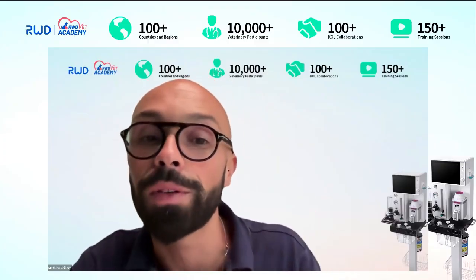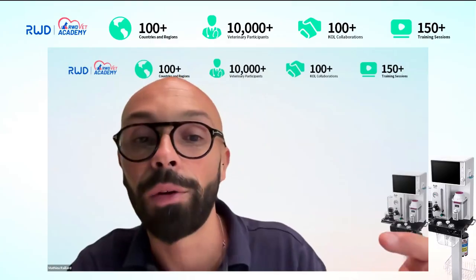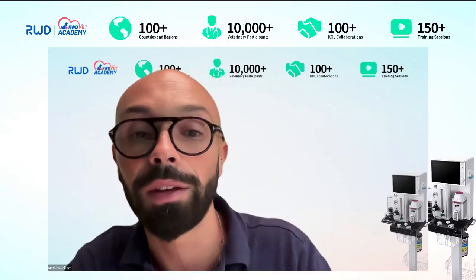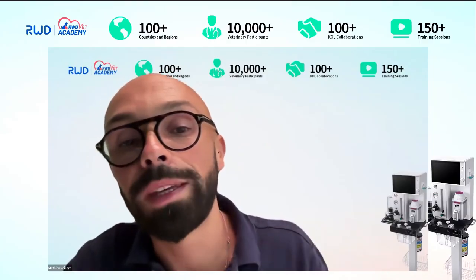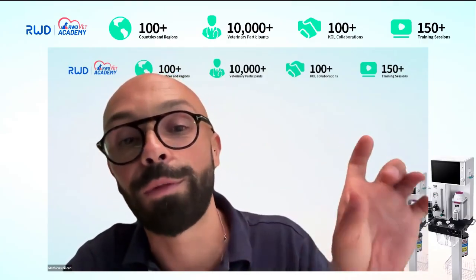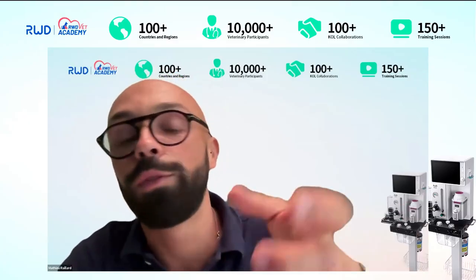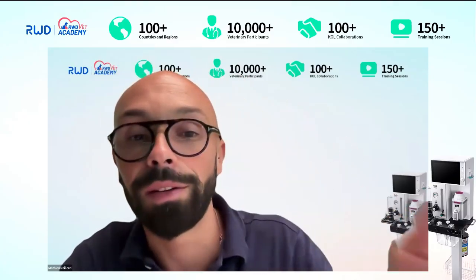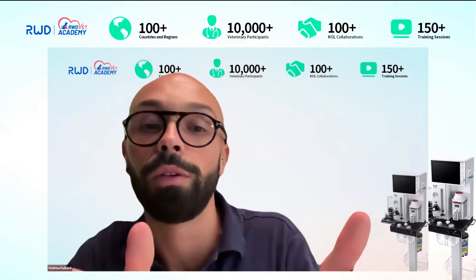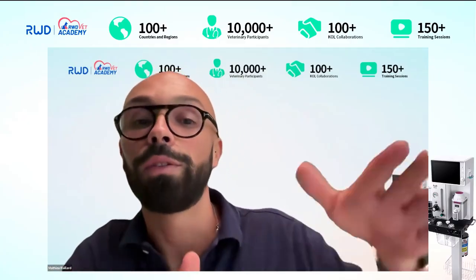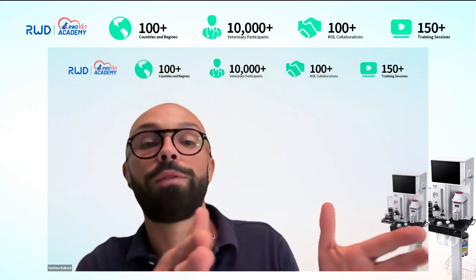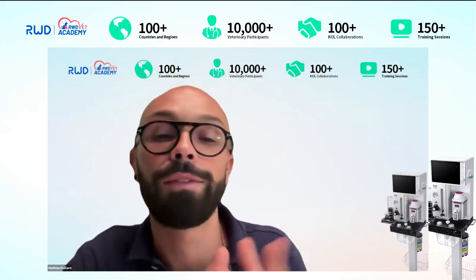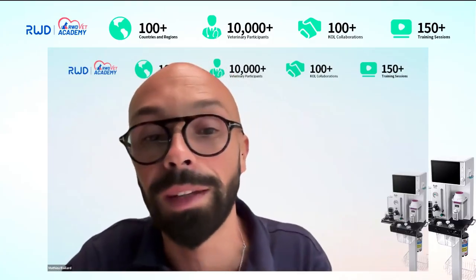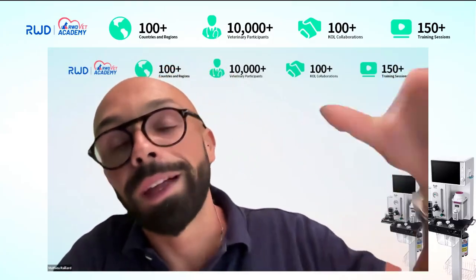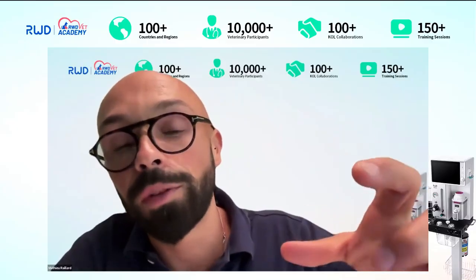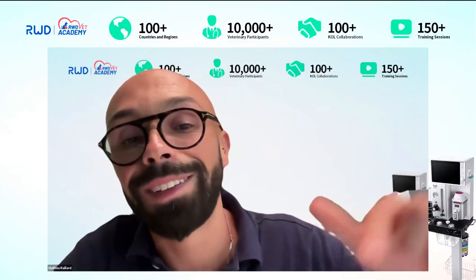Now, the problem is that the animals that need assistance when they start taking a breath will need to have a peak inspiratory flow within the first 30% of their inspiratory time. If you take, for example, a cat that needs that, we are talking about a full inspiration of 300 milliseconds. So if I have a third of that, I need my peak inspiratory flow at 100 milliseconds, so 0.1 seconds after the animal has started to take a breath.